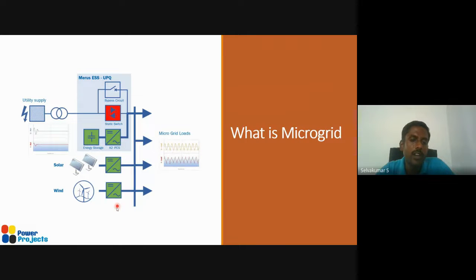you have a diesel generator in your college campus, as soon as the grid fails, your power will go off, then the diesel generator will be manually switched on, or if it has an automatic mains failure, it will switch on automatically. But there is about a 10 to 20 seconds delay, even if you have an AMF, and the loads will face about a 10 to 20 seconds interruption. That's the time taken between the grid failure and switching on the diesel generator automatically. And if it is manual, then it depends upon the operator's effectiveness, right?